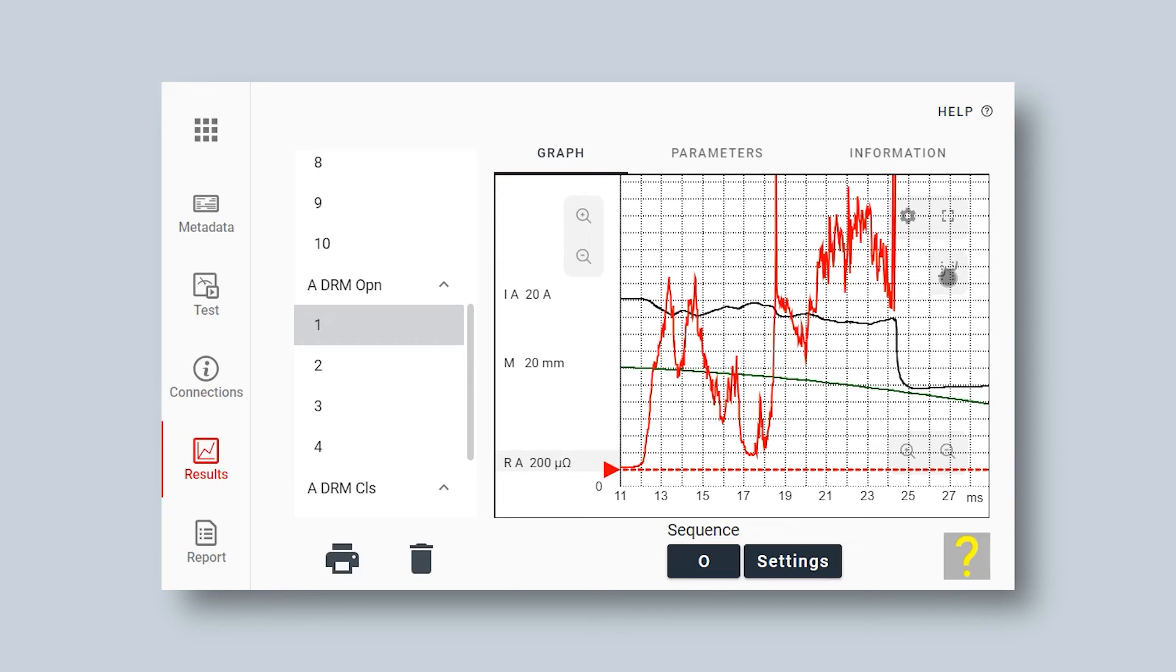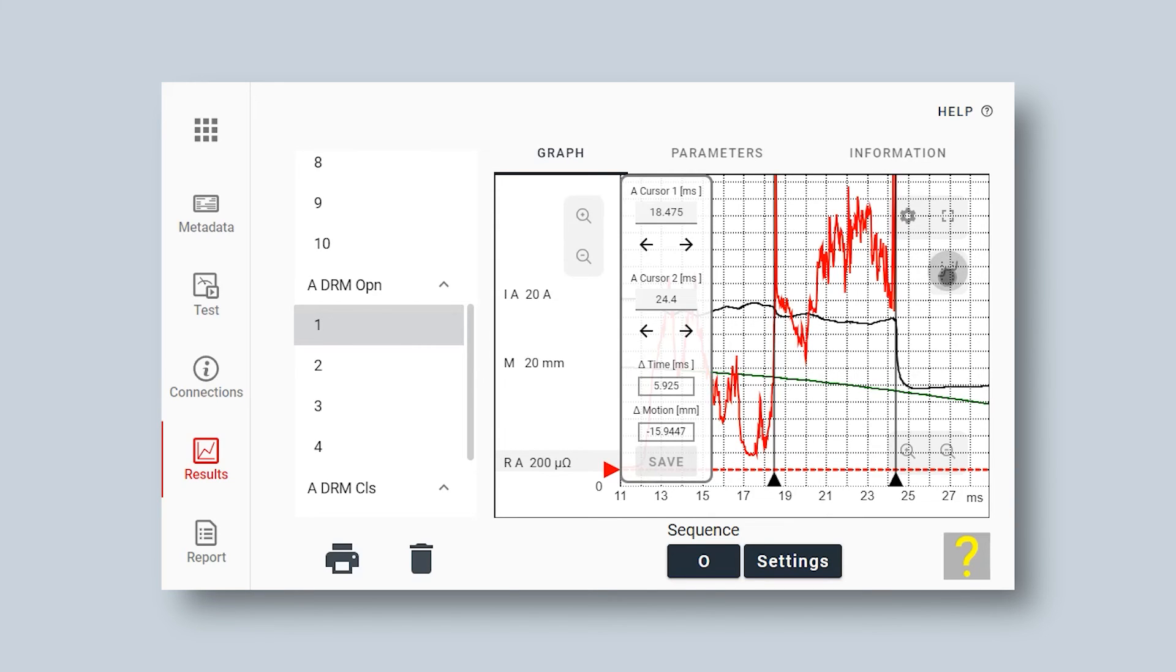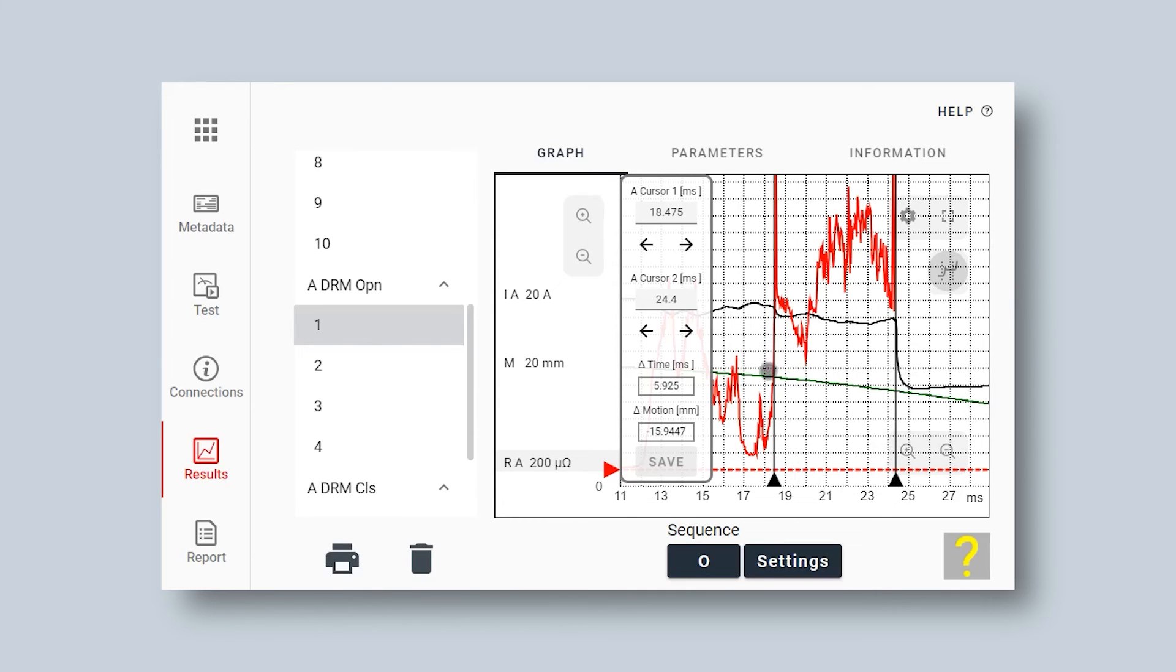I'm starting to adjust my cursors to find my two arcing points. I can see here that my two cursors are quite well placed on the red graph. I have one at the main contact release at 18.5 milliseconds and one at the arcing contact release at 24.5 milliseconds.